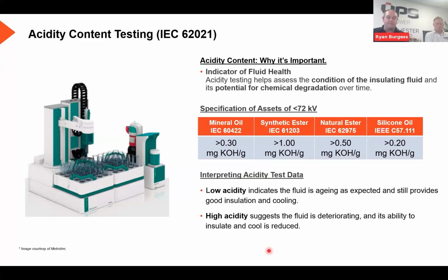And the reason for the different limit is, again, due to the types of acids that are formed during the aging process. So again, we're just going to compare mineral oils and synthetic esters. Mineral oils produce shorter chained acids, which are more readily absorbable in the water, which are then more readily absorbable into the cellulose insulating material. So that means you need a smaller amount for them to be harmful, whereas esters produce longer chained acids, which don't readily absorb in water. Because of that, you need a higher amount of them to become damaging to the paper over time.